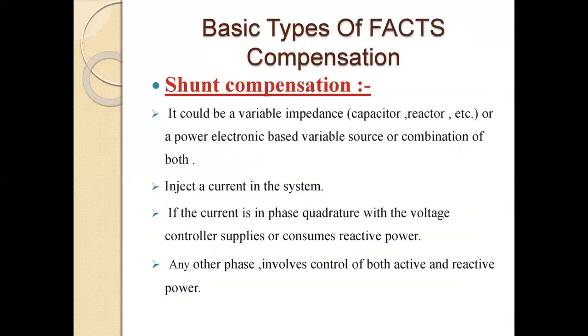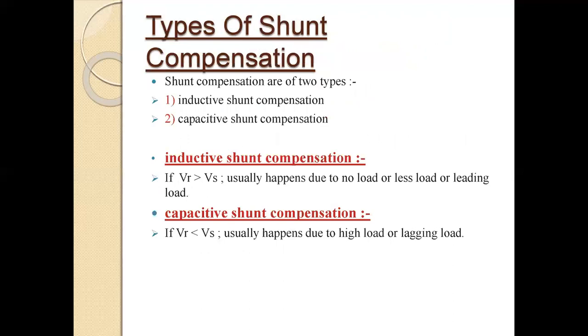Now we discuss shunt compensation. It could be a variable impedance, capacitor, reactor, or a power electronic based variable source, or a combination of these. It injects a current into the system. If the current is in phase quadrature with the voltage, the controller supplies or consumes reactive power. Any other phase involves the control of both active and reactive power. There are two types of shunt compensation: first, inductive shunt compensation, and second, capacitive shunt compensation.